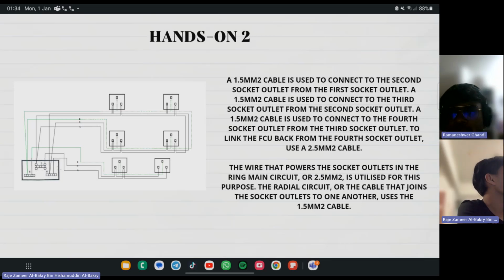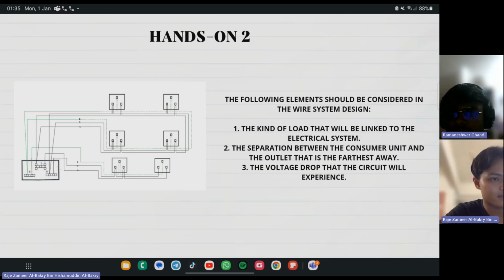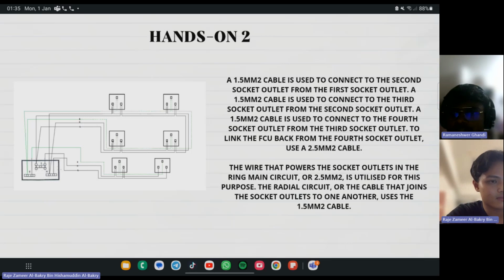A 1.5 mm square cable is used to connect the second socket outlet from the first socket outlet. A 1.5 mm square cable is used to connect the third socket outlet from the second socket outlet. A 1.5 mm square cable is used to connect the fourth socket outlet from the third socket outlet. To link the FCU back from the fourth socket outlet, use a 2.5 mm cable. The wire that powers the socket outlets in the ring main circuit, or 2.5 mm square, is utilized for this purpose. Radial, or the cable that joins the socket outlets to one another, uses the 1.5 mm square cable.